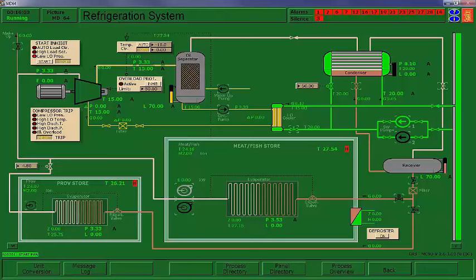We need to put on each of our diffusers. And then when we come back, make sure and put this lube oil circ pump on. That has to be on. And we don't want to put too much load on this compressor on startup, so I leave it in manual and I put it in about 25%. All right. Once we start the lube oil pump, our trips should all clear here. We can go ahead and start it.